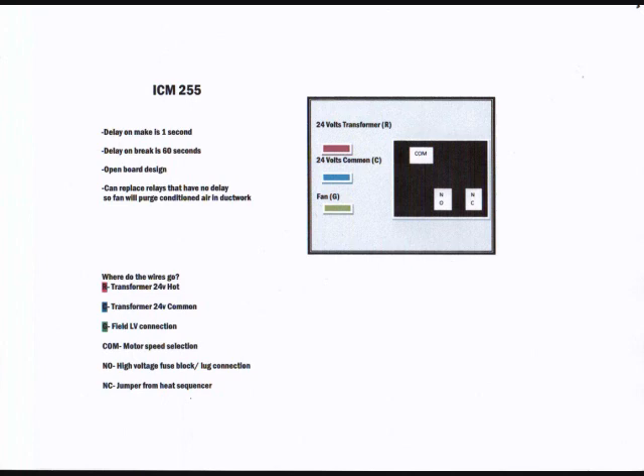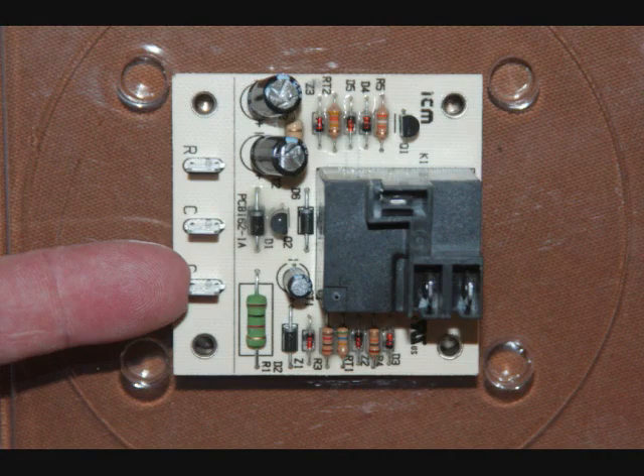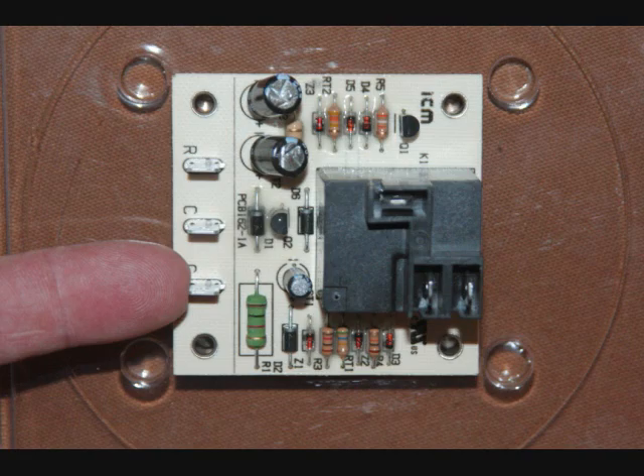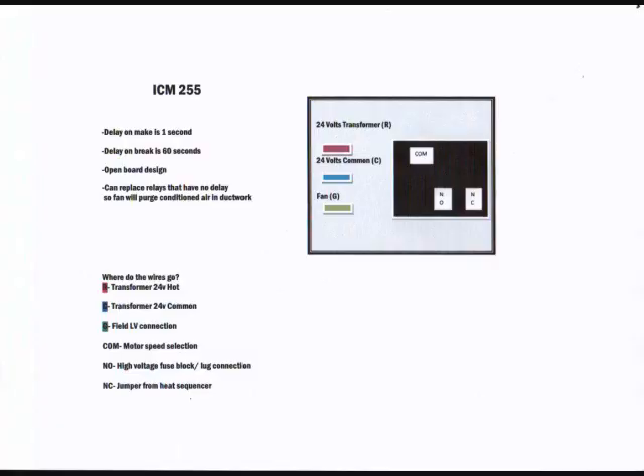The last low voltage wire is the green or fan wire. Sometimes it's black. I've noticed over the years, I think on Trane it's black. And it will go back to the low voltage field connection right where you wire it up when you install the unit with your wire nuts or whatever you use. And there it is right there.